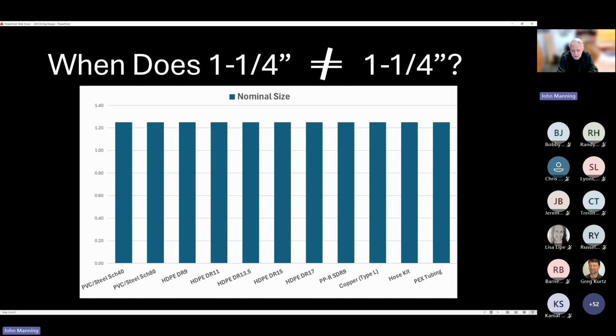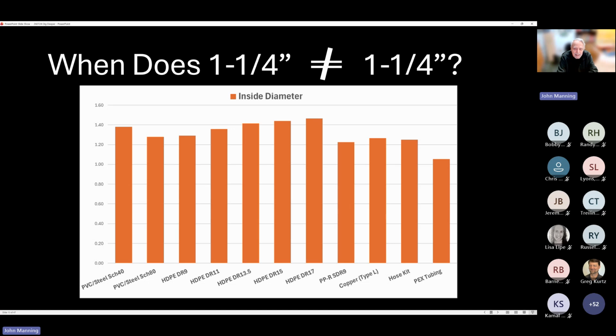The backbone of our industry is high density polyethylene in a variety of diameter ratios. Polypropylene has certainly shown up on quite a few jobs. Certainly copper, hose, and PEX tubing. All these materials are available in 1 1/4 inch, but 1 1/4 inch doesn't always equal 1 1/4 inch. So for these different pipe materials, the inside diameter is different. And is it inside diameter that's important?